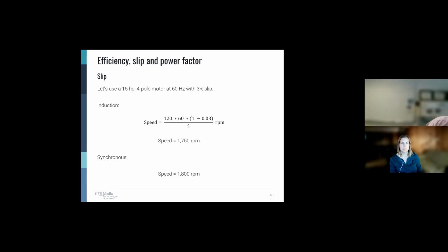It runs at 1750. So why do we care? Well, if we're specifying a motor to run a fan or a pump, the mechanical engineer or the hydraulic engineer is expecting that fan to deliver a certain flow, and that flow is directly proportional to the speed of the fan. And that 50 RPM will move us on the fan curve or the pump curve. It may not be significant, but then again, it may be. So it's just something to be aware of.